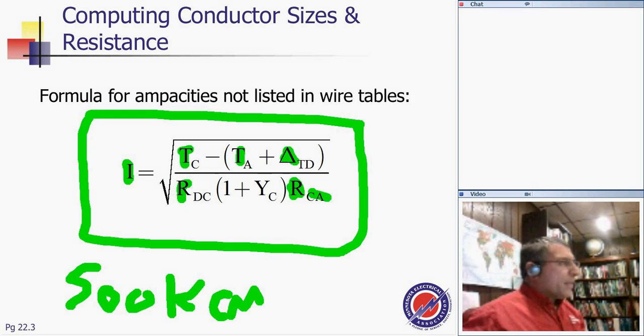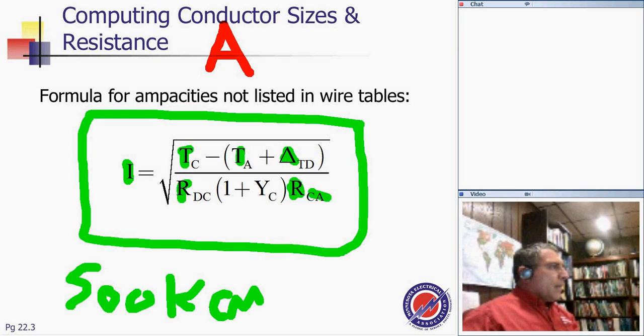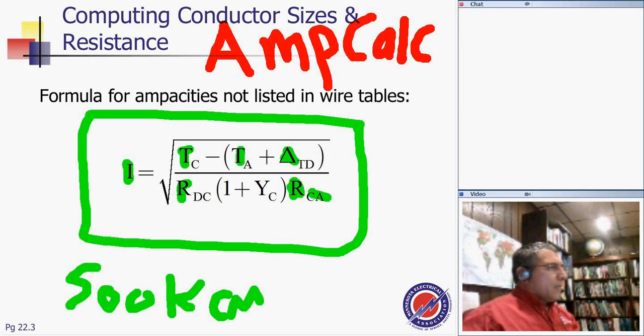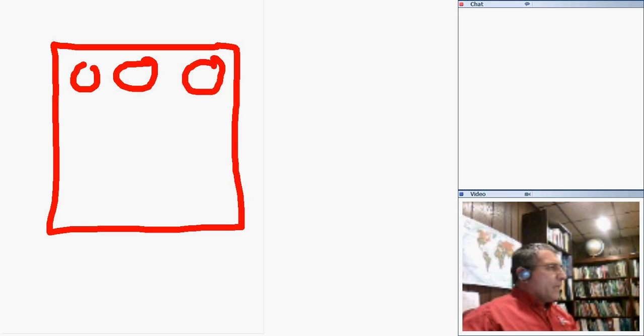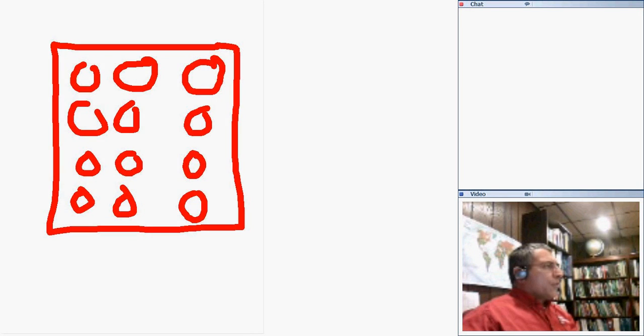If you remember, guys, a long time ago, I think I told you there's a software called AmpCalc. AmpCalc is a software that allows you to size the conductors and find how much current they can carry if you put them in an underground box. Suppose you have 1, 2, 3, 4, 5, 6, 7, 8, 9, 10, 11, 12 ducts. Each one of these is carrying three conductors, and each one of these is 600 kcm. And let's put a neutral here. Here's one neutral, and that neutral happens to be 400 kcm, and one neutral 400 kcm. Okay.